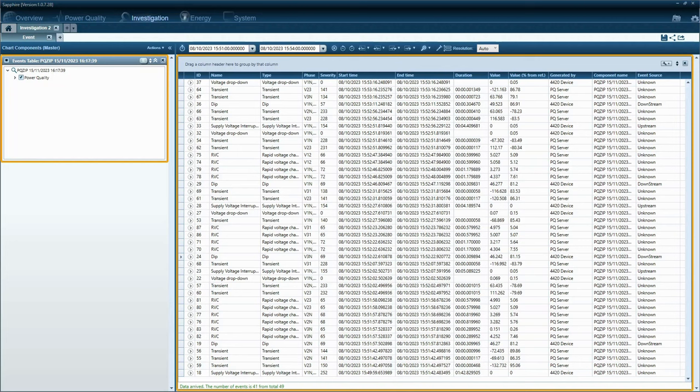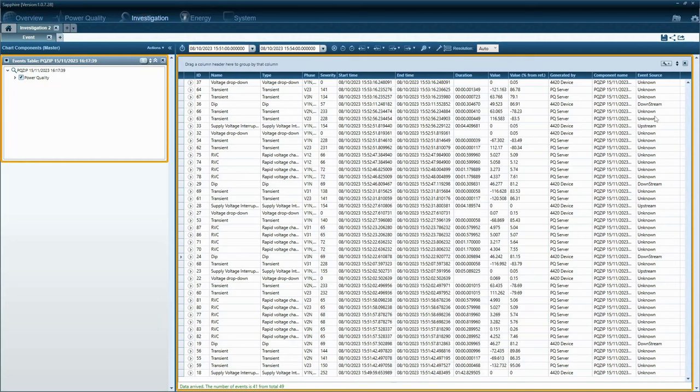PQ SCADA is equipped with a unique capability to recognize event sources, categorizing them into three distinct classifications. Upstream represents events originated from an external network, like your electricity supplier. Downstream represents events stemming from an internal network, like your own wiring.